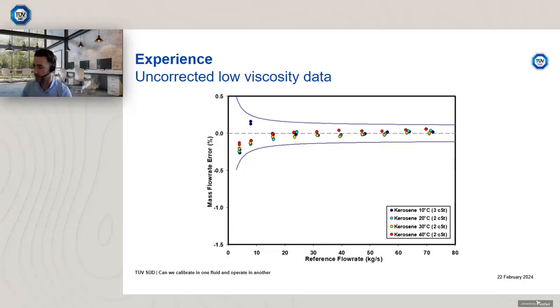So you can see we have dark blue circles, which is kerosene at 10 degrees C, and we also have kerosene at 20, 30 and 40 degrees C. On the x-axis we have the reference flow rate, so that's our reference, whether it be the secondary reference in this case, which was a positive displacement meter pre-calibrated against a gravimetric system, or simply the gravimetric system, the mass with respect to the time given as our reference flow rate.